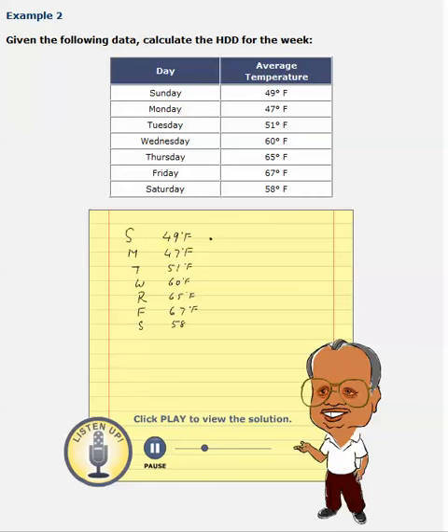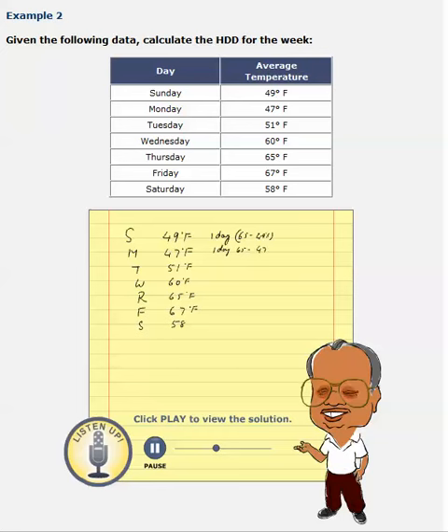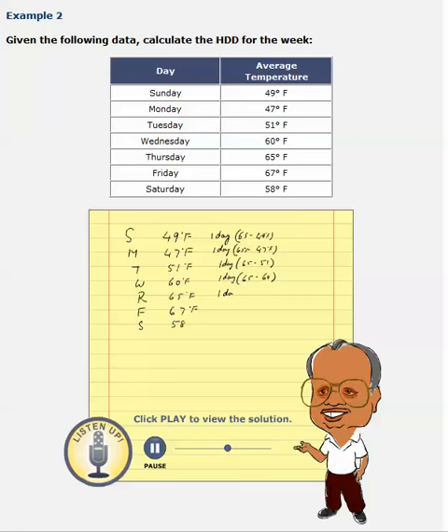So we need to calculate heating degree days for each day. For Sunday, the outside temperature gives you 65 minus 49 degree days. Similarly, one day times 65 minus 47 degrees Fahrenheit. One day times 65 minus 51. One day times 65 minus 60. And one day times 65 minus 65, which will be 0.